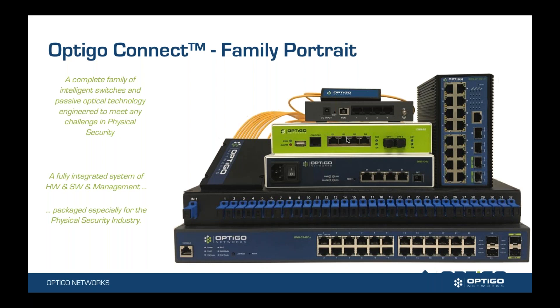The second thing we do is not duplicate an IT network for the OT, because that would cost far too much money. We're not going to take large Cisco and HP switches that are geared for IT and plop them over to the OT just because they pass traffic. What we've done is take network switches and splitters that are specifically tailored for this industry, so you're not paying for a switch where you're only using 5% of the functionality. The green unit is our head end — that's what starts the network. The blue units — a 16-port and a 24-port — are our edge switches, connecting into devices via RJ45.